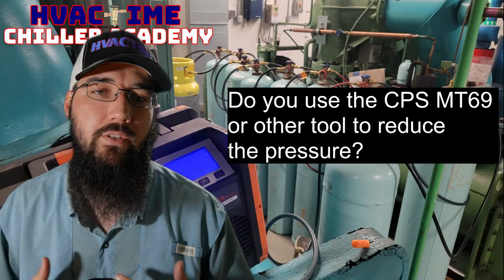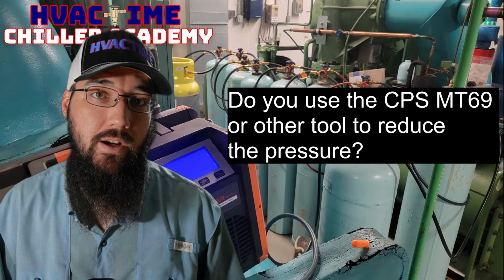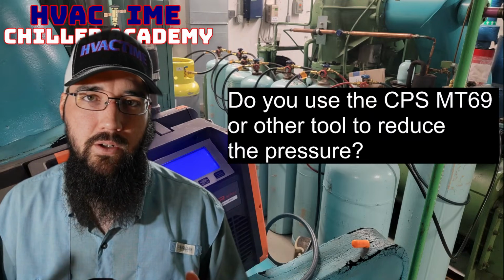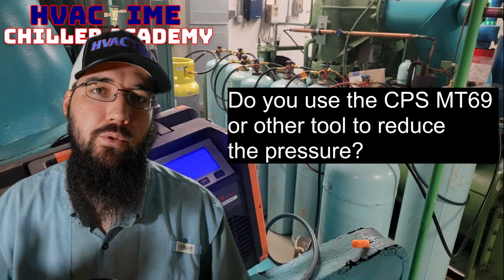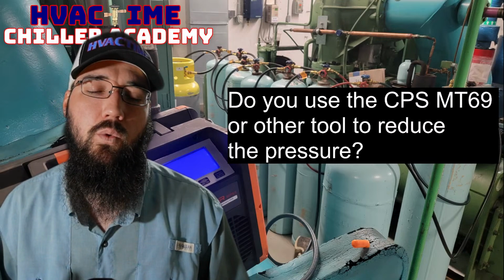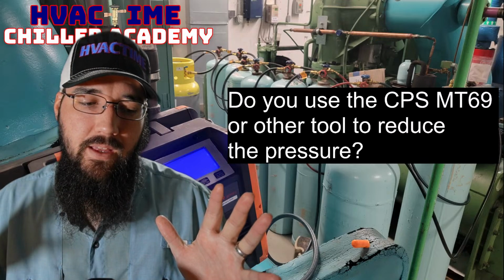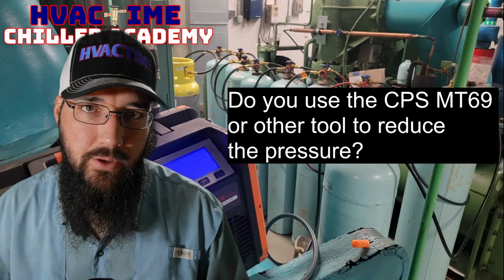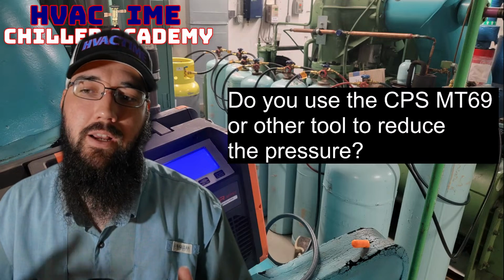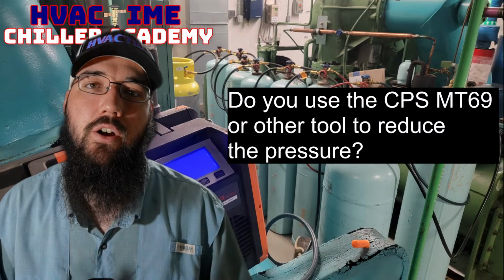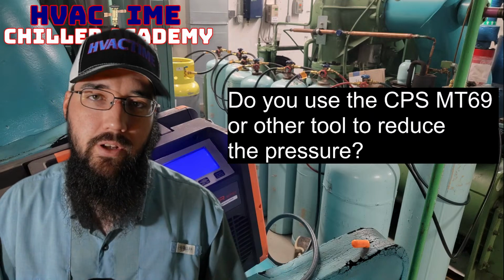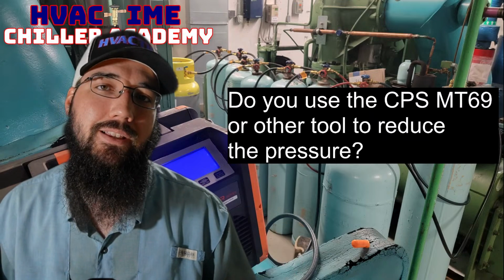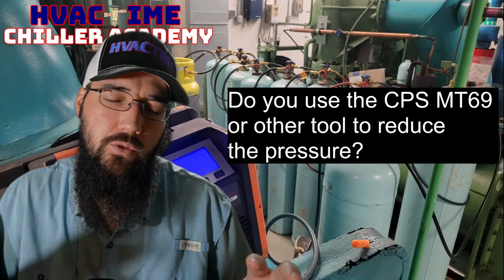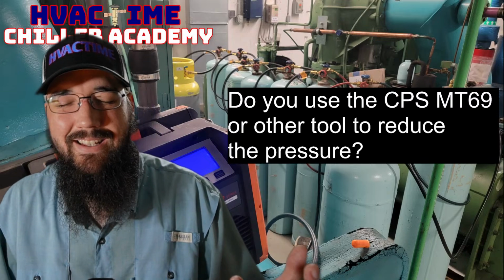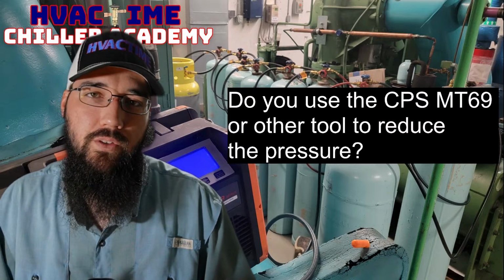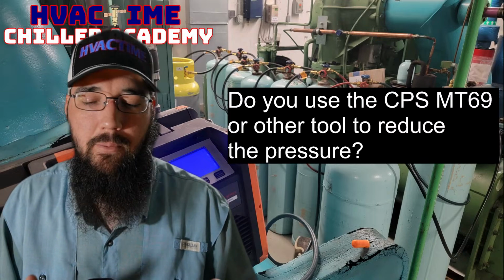I've made my own. I've got a few different versions of it I've made. So I came up with a design for a braze plate one. Now, I'm not the first person in the world to ever come up with that. And I've had a few people take that design and iterate it for themselves as well. And so having a subcooler is extremely important, especially if you're doing an outside recovery of any kind on a high pressure refrigerant. You really want some way to be able to de-superheat that refrigerant. And we call it subcoolers or subcooling because we technically do get it to, or at least the good ones will get it back into a liquid state lots of the time.